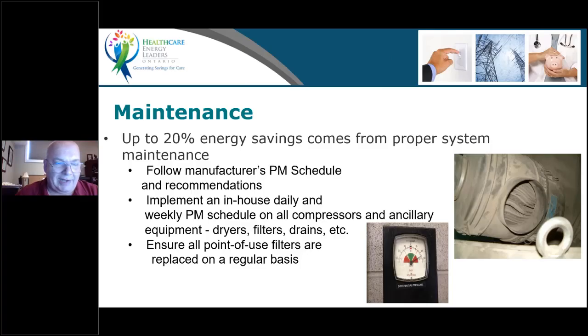Maintenance is another issue, and believe it or not, lack of proper maintenance on a compressor, whether it's reciprocating or screw, does affect the performance and the kW demand on the compressor itself, such as differential pressures across my intake filters. As you can see, this one is completely plugged, so this compressor was starving itself. High differentials across filter elements. Filter elements, point of use filters, inline filters, all need to be part of a regular PM program. Not just changing oil on a compressor, but everything associated that comes down to pressure restrictions and back pressure. So it's important that customers follow a PM schedule specific to their compressor, with in-house daily checks and weekly checks on things such as the dryers, the filters, the drains, to make sure they're all working properly. And again, all point of use filters are replaced on a regular basis. They've always been neglected, those little point of use filters.